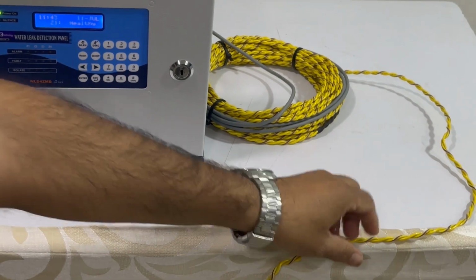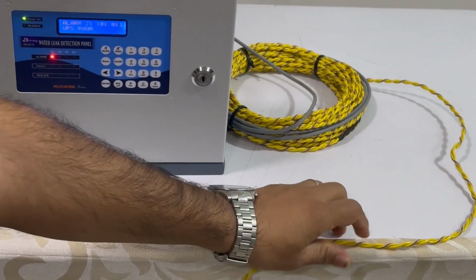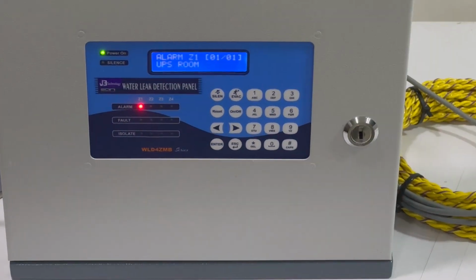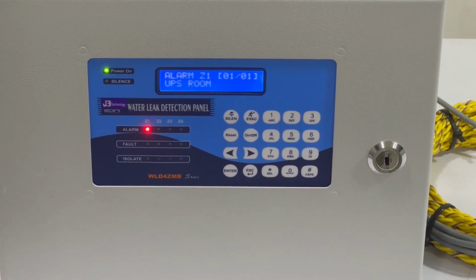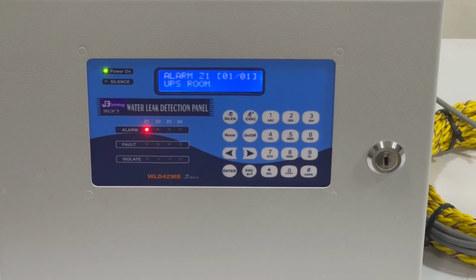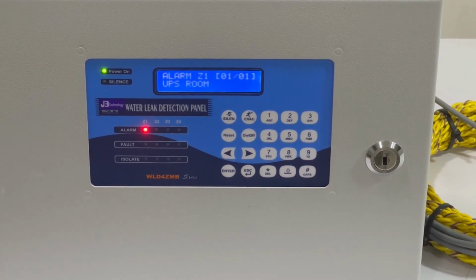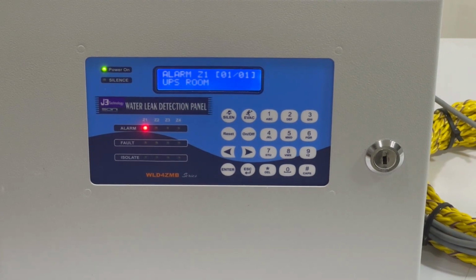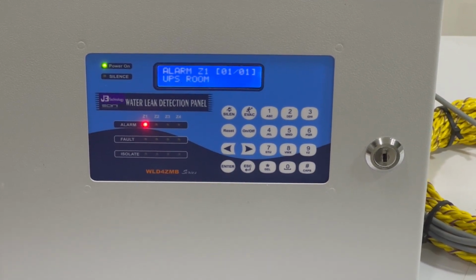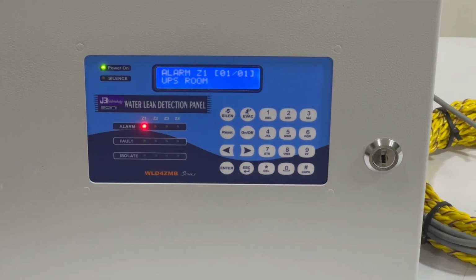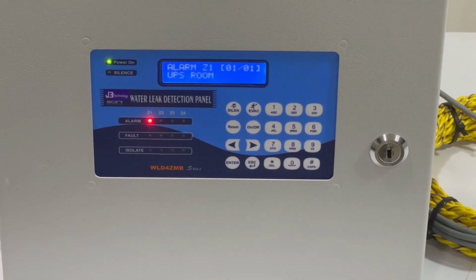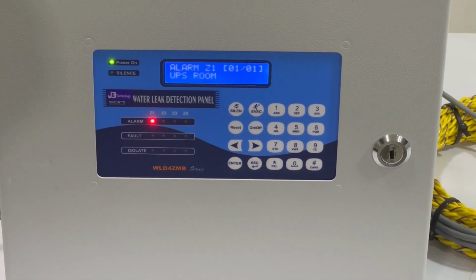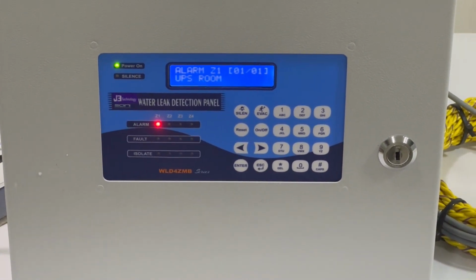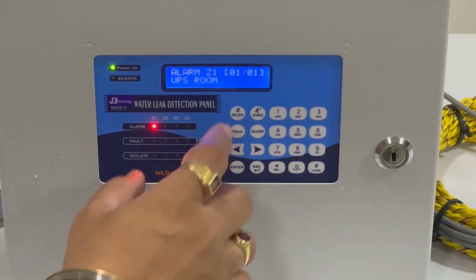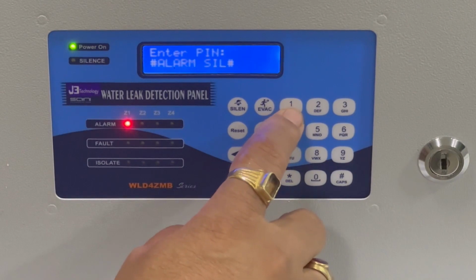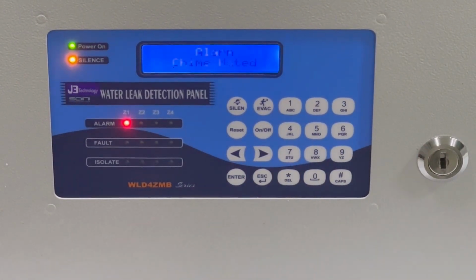I can check again. Okay. It will not silence automatically. I have to manually silence that panel. It will go on continuously unless I manually silence the panel. It will continuously go on. I have to silence it manually. For silencing manually, I just have to press the silence button. It will ask for the password. Just 1 2 3 4. The panel gets silenced.